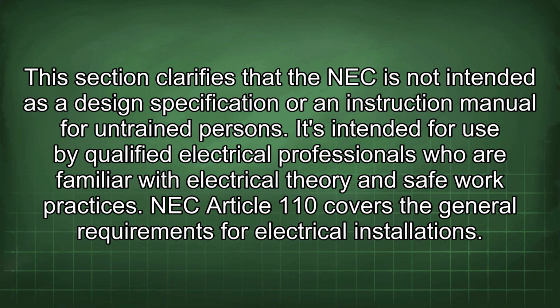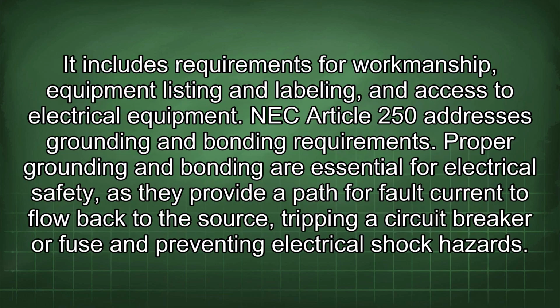NEC Article 110 covers the general requirements for electrical installations. It includes requirements for workmanship, equipment listing and labeling, and access to electrical equipment. NEC Article 250 addresses grounding and bonding requirements. Proper grounding and bonding are essential for electrical safety, as they provide a path for fault current to flow back to the source, tripping a circuit breaker or fuse and preventing electrical shock hazards.